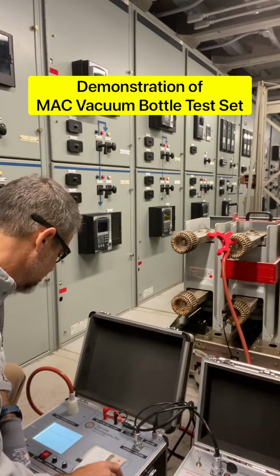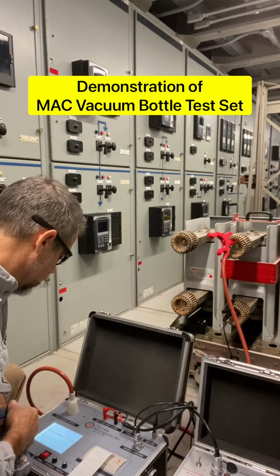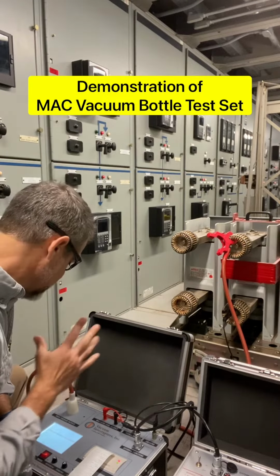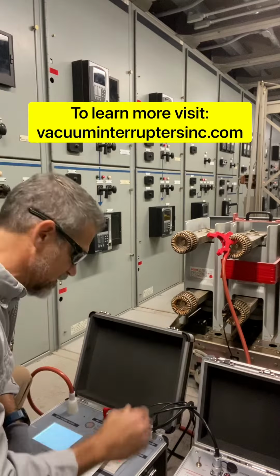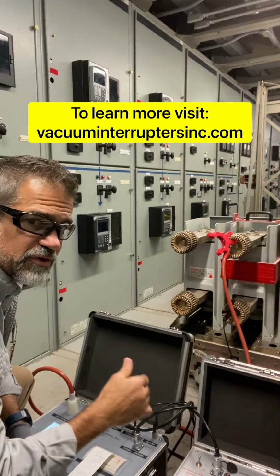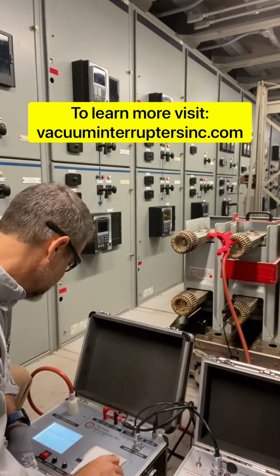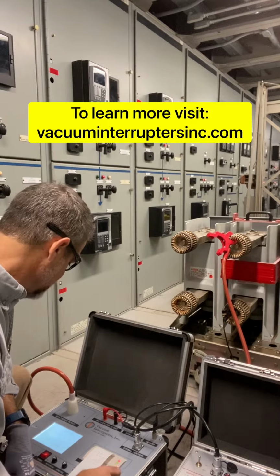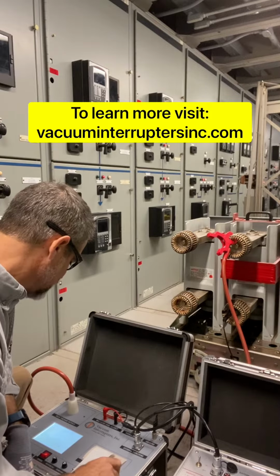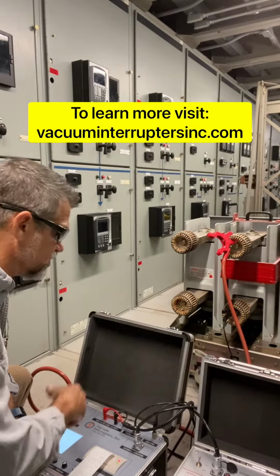We've got the VI test. We're going to select the rigid coil. We're going to select 25 kV for this particular test and a curve of 8. If you're ever not sure which curve to use, give us a call and we can help coach you through that. Then we just select run, we select OK, and now we can begin to run the test.